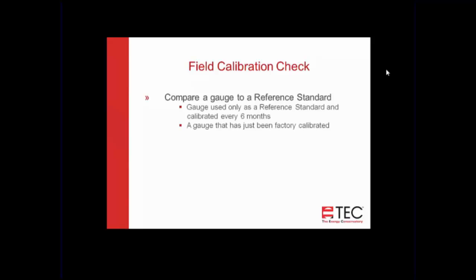Another option, if you only have a couple of people with gauges or just one person with a couple of gauges, is to send one of them in for calibration and then use that as a standard and check it against another gauge before it gets out in the field again. So these two methods give you a lot of flexibility in using a gauge that you know is within calibration spec to check another gauge to see how that one's doing.